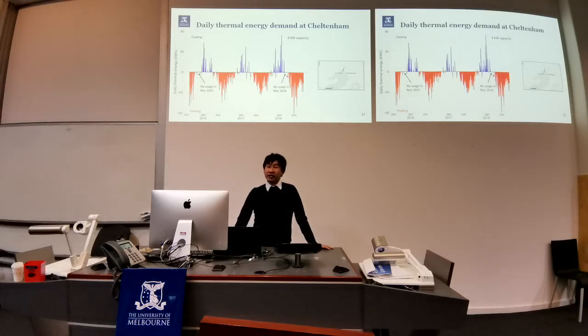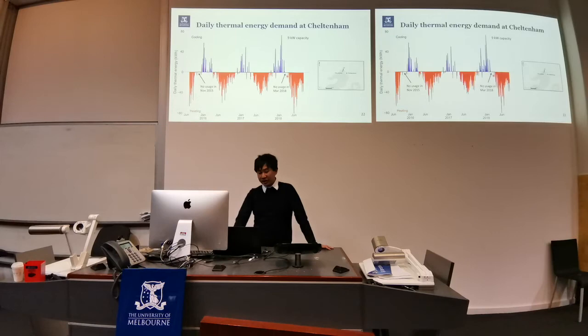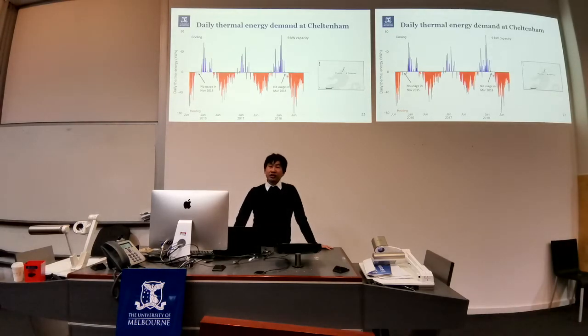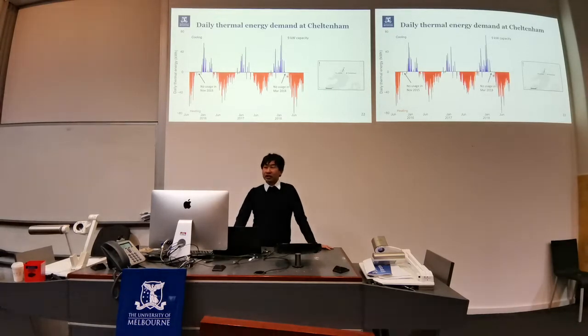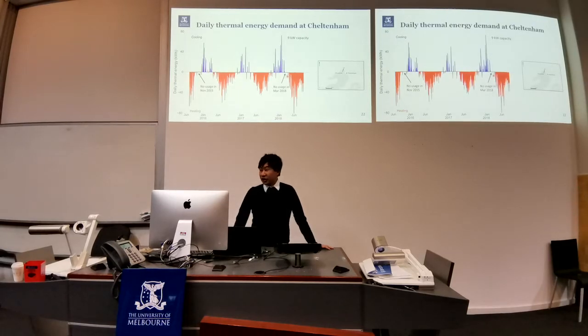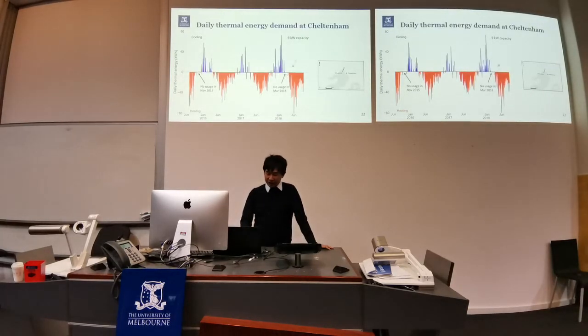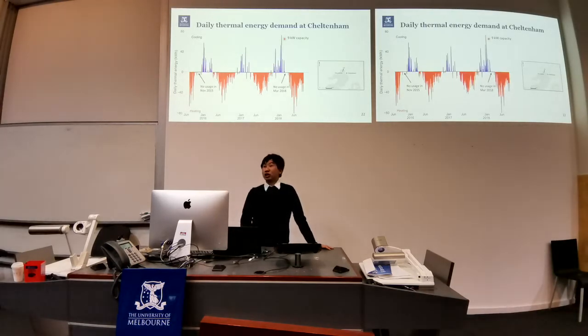It turns out that the temperature was nice enough that the occupiers did not use any additional heating and cooling system. It was enough to just open the window for fresh air. Overall, it was discovered that in this property, the heating and cooling system was only used about 6% of the year. One example is on this day, when the daily thermal energy is the highest, just under 80 kilowatt hours. For a 9 kilowatt system, this means that the system only ran about 9 hours in a day at equivalent full load capacity. This means that for the rest of the time, either the system was not used or did not operate at full capacity.